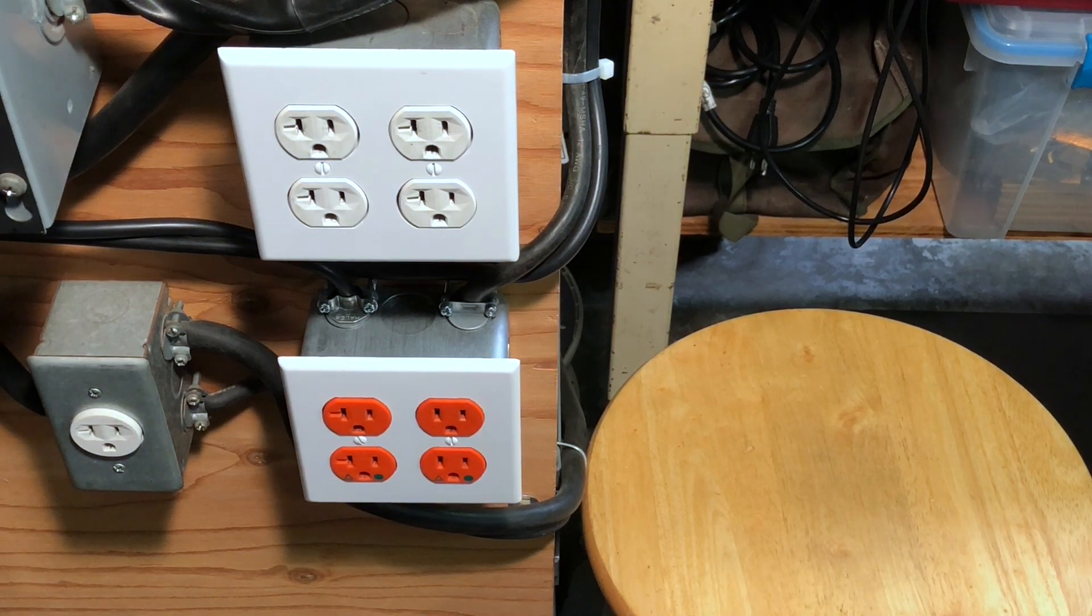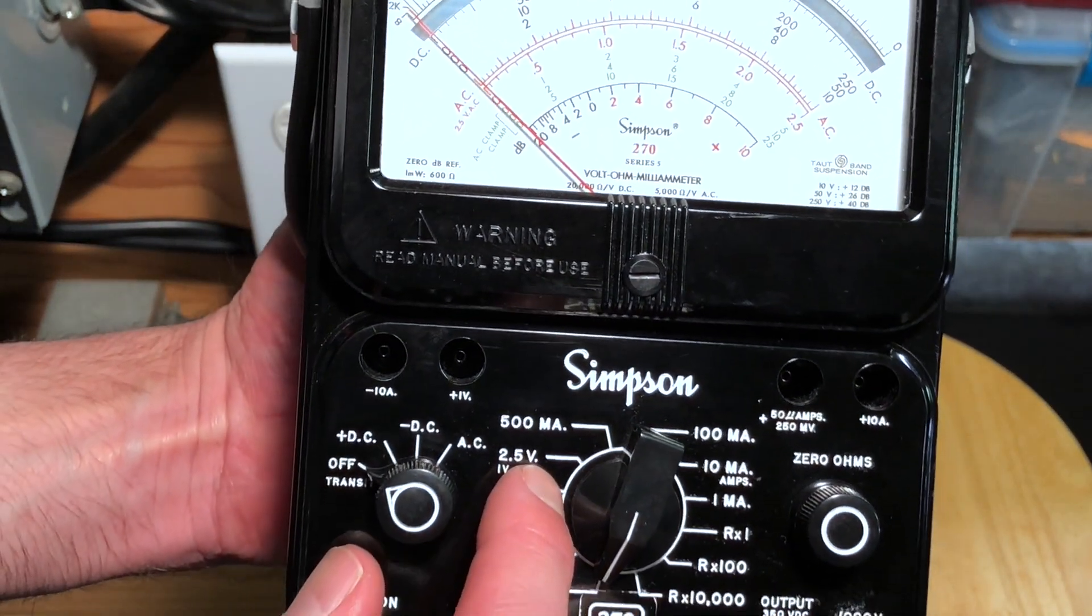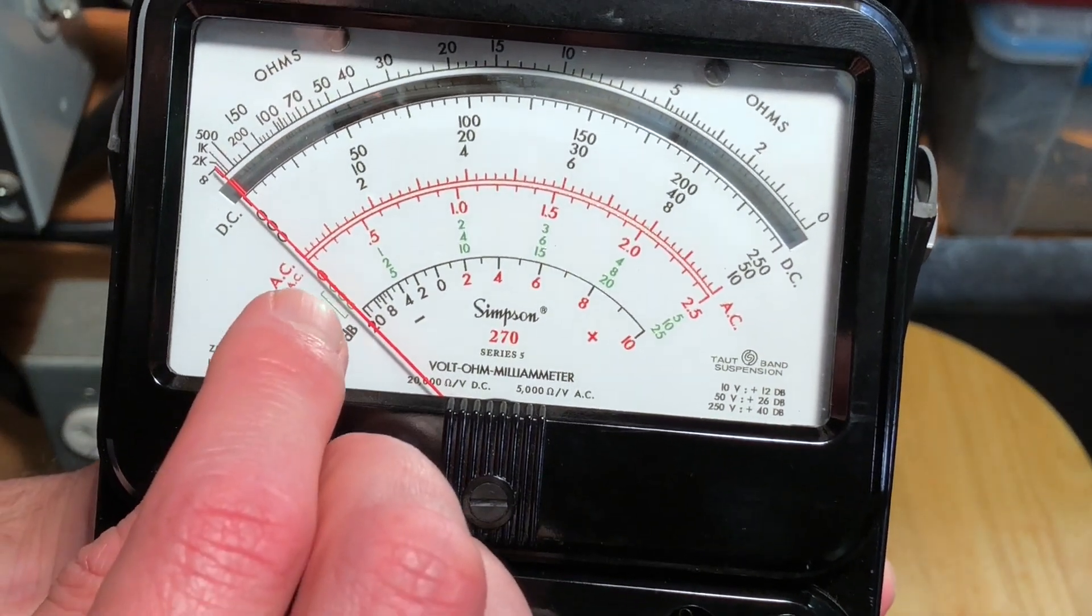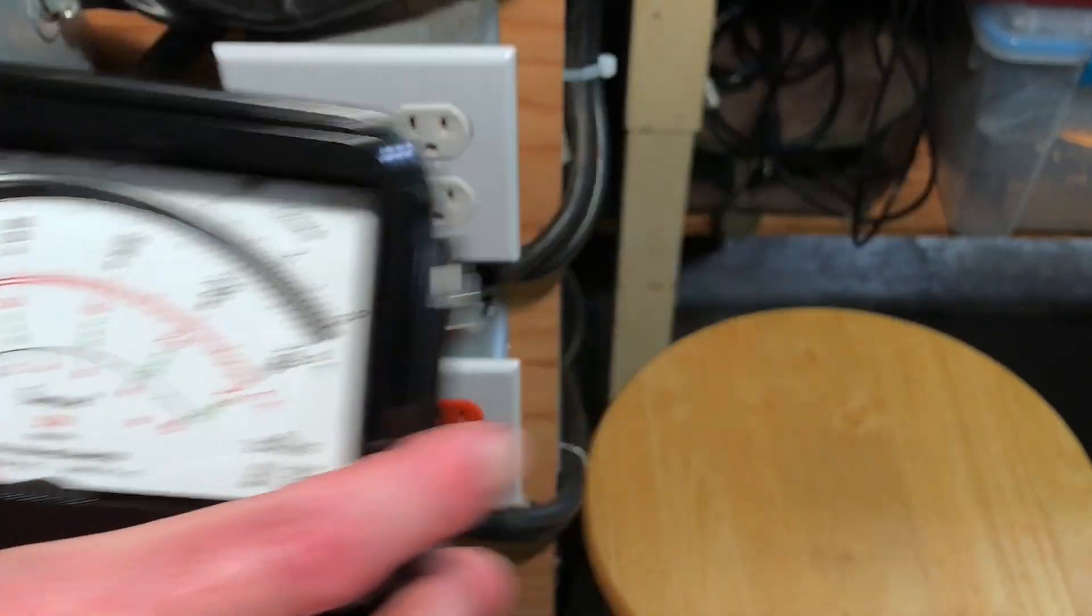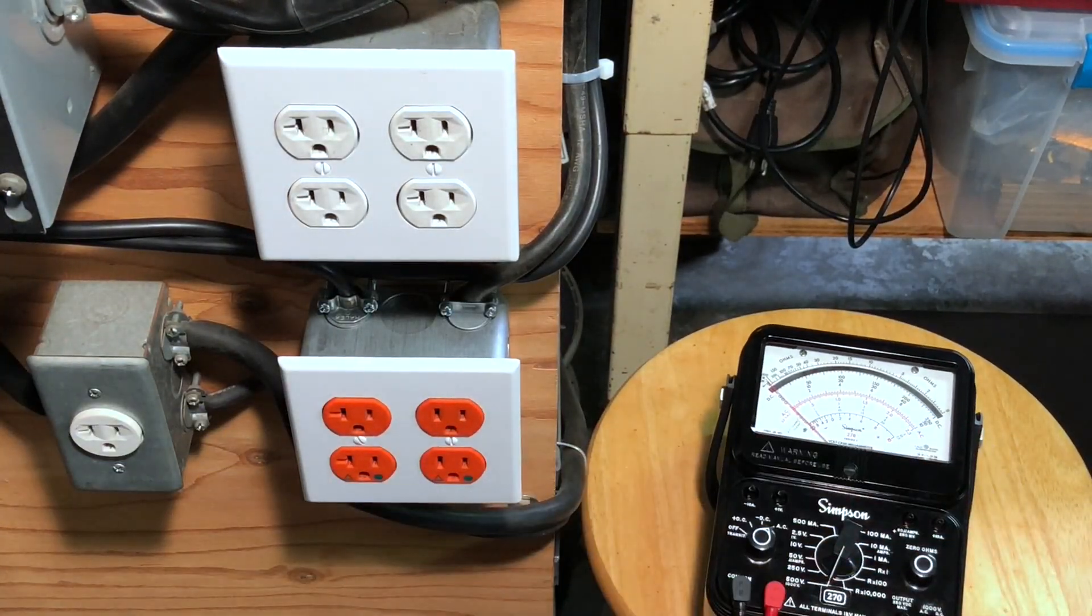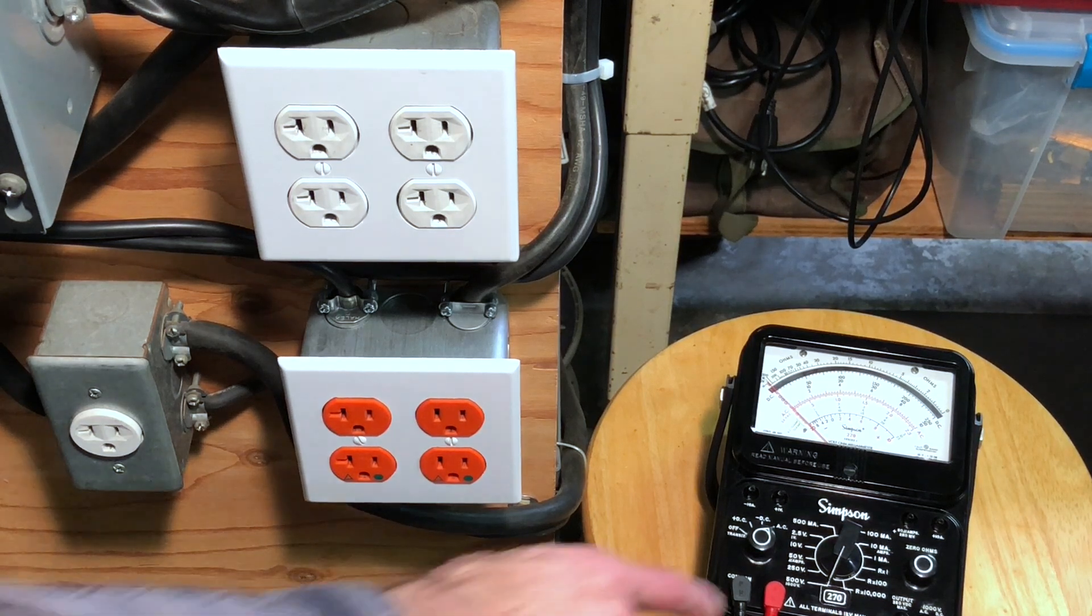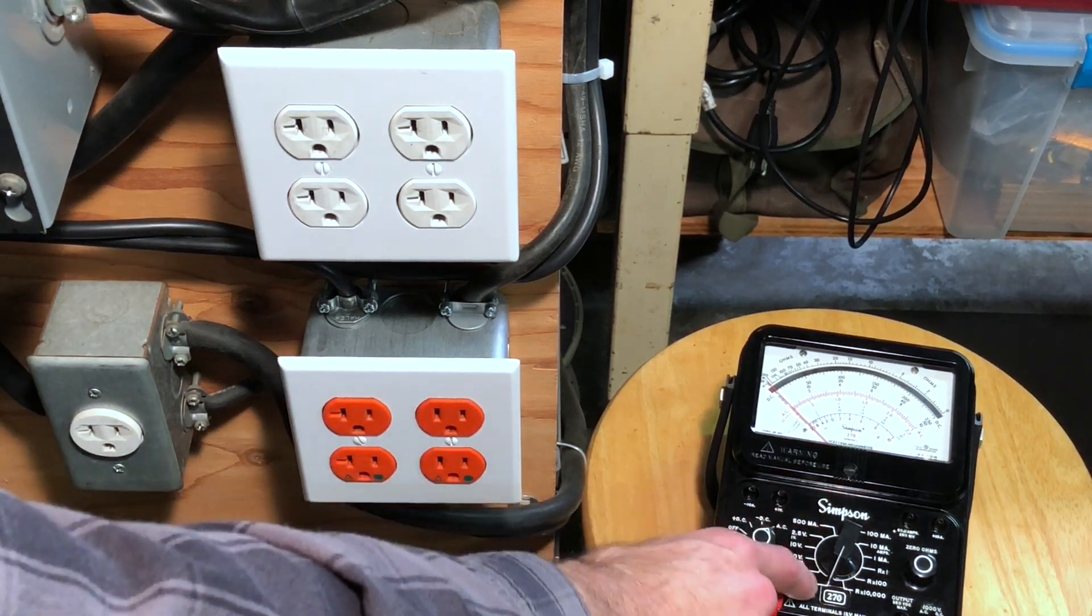Let me grab my Simpson 270 meter from the shelf. We'll be using the 500 volt range down to the 2.5 volt range, and we'll set this over to AC volts. You can see the impedance on AC is 5,000 ohms per volt. On AC, this red scale here, the lower red scale is for 2.5 volts, and then the other ranges use the upper red scale with the numbers written in black. What that 5,000 ohms per volt means is that the impedance of the meter can be figured out by multiplying the voltage you're on. For example, 500 volts multiply that by 5,000, you get 2.5 mega ohms.